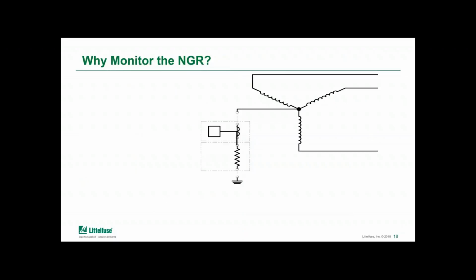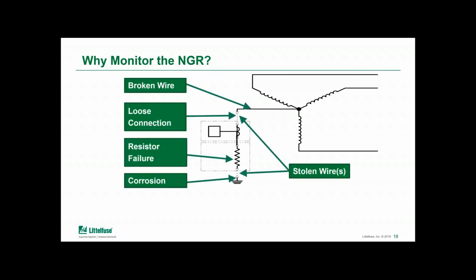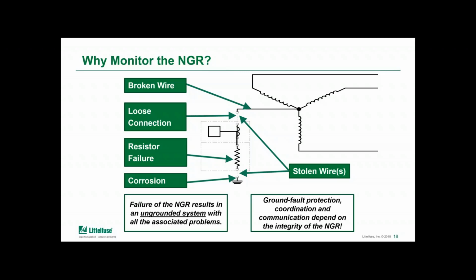So when we look at resistance grounding, all of those advantages come with one disadvantage, and that is that the resistor has a possibility of failing open, due to mechanical damage, or perhaps due to a fault that was present on the NGR for longer than the time rating of the NGR itself. Now there are more pieces in the grounding connection as well, and those could also fail. So that could be a broken connection wire, or just a loose connection after maintenance. One other possibility highlighted here is corroded ground electrodes. And in some cases, we've even heard customers talk about stolen grounding wires. Any of those failures can result in the system being ungrounded.